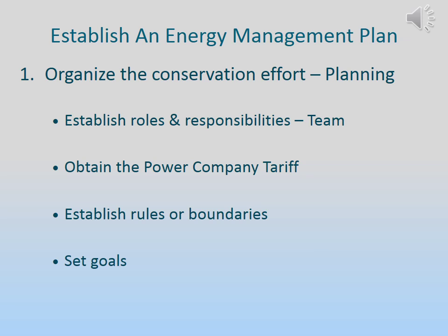For example, let's say we have a strategy where we do not run two XYZ pumps at the same time. All we need is one mechanic to make a mistake and run two pumps during a maintenance check, and there goes our ECM savings. Working in a team changes the way we have to handle things. We must have procedures established that state clearly, unless this is going on, this does not happen. We have to have everyone on the same page. If we have a big plant or multiple people involved, everyone needs to know what the strategies are and what we are trying to do.